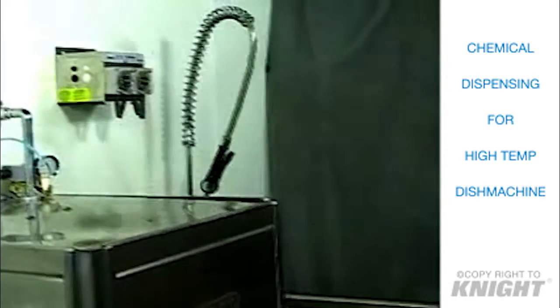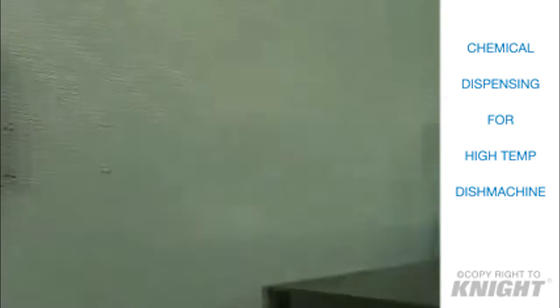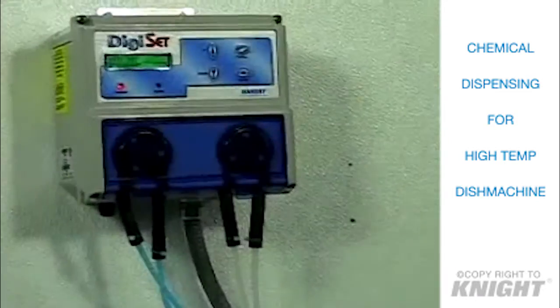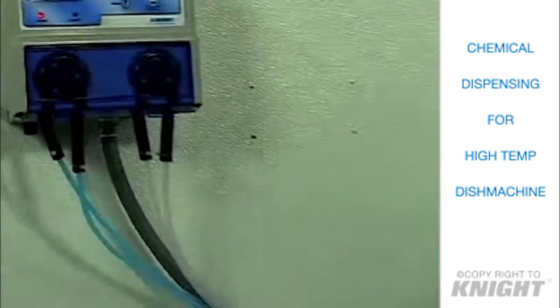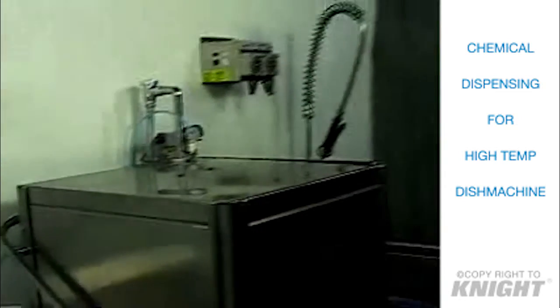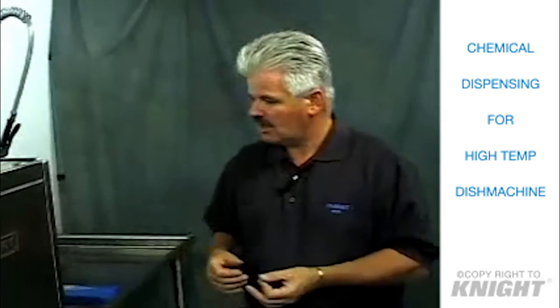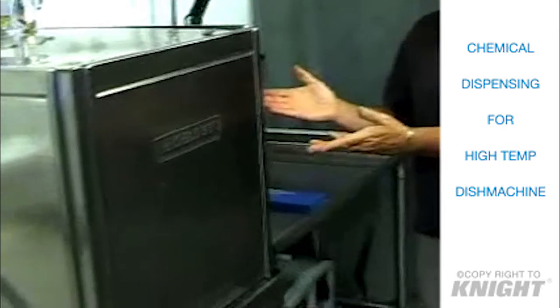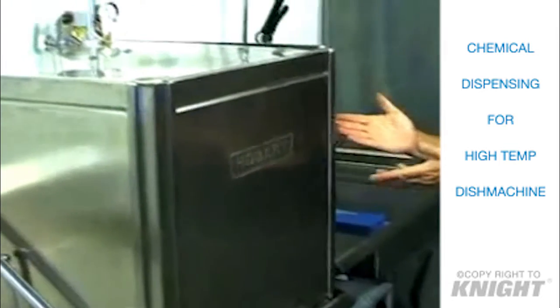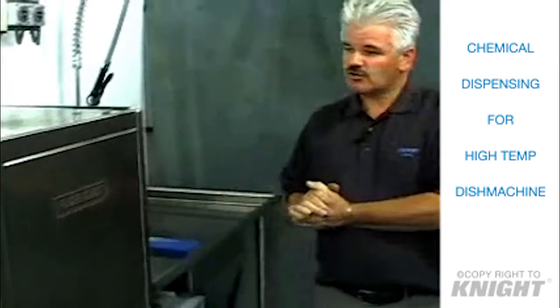If I let my detergent pump run for 1 minute and find out what my flow rate is, and let's say for argument's sake that my flow rate is 6 ounces per minute, that means for every 10 seconds the pump operates, I get 1 ounce of product. If I'm working on this dish machine and I know, for example, that this machine holds 16 gallons of water, if I wanted to titrate this machine at 1/4 ounce of chemical per gallon, that would mean I'd have to add 4 ounces of chemical.